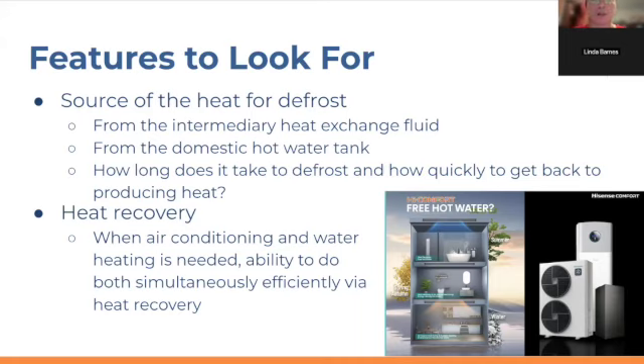But do all the manufacturers of these products do that? No. So you have to ask, okay, how is the system set up, and what kind of software logic do they have set up to do the defrost? Another thing is heat recovery. I mentioned that a number of the refrigerant split systems in combi can do heat recovery. Some people question whether heat recovery is really that beneficial, or is it just an advertising thing to differentiate yourself, but in reality, the energy savings is actually pretty small.